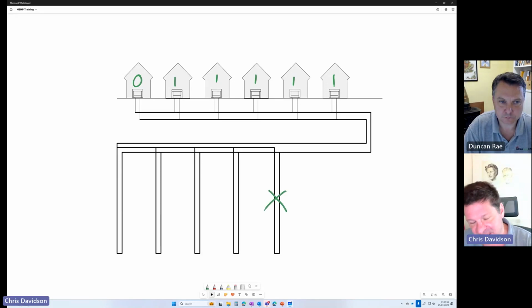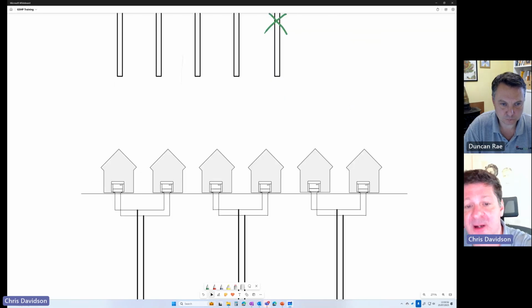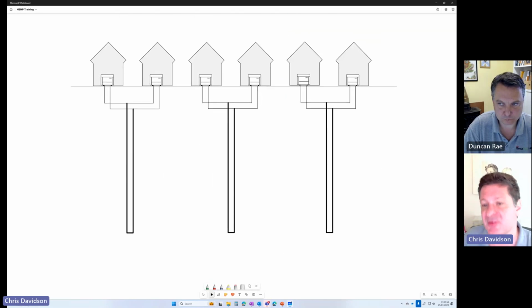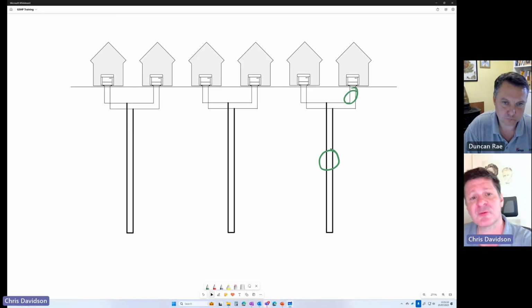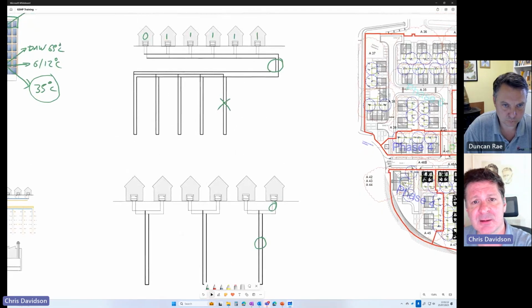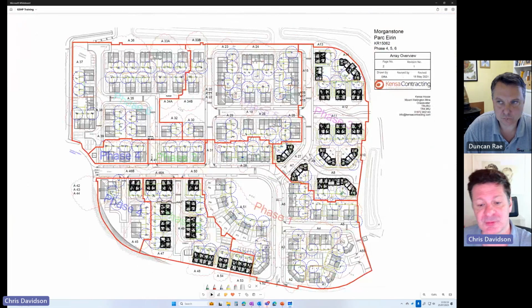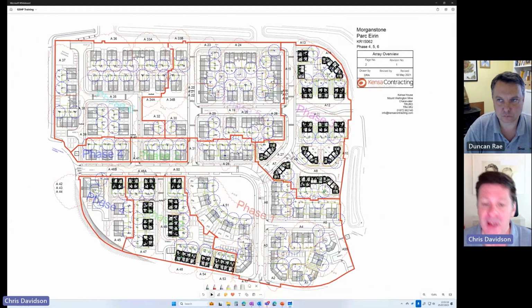The downside, however, of connecting all these together is that these header pipes start to get very big. So there is a balance between connecting more buildings, more heat pumps, getting greater diversity, but then pushing your headers up. An alternative is to break a heat network like that up into pieces. So in this case, we've got maybe one borehole between 2 dwellings. And in that case, this collector pipe might actually be bigger diameter than the header pipes themselves. So we've got a balance between the two approaches. And in reality, of course, good engineering, you make compromises and you do a bit of both.